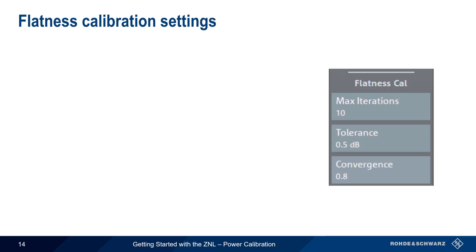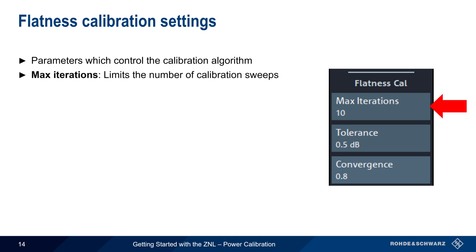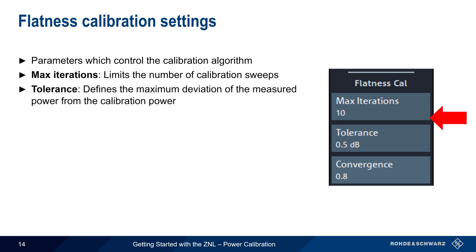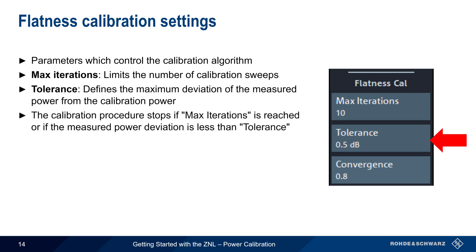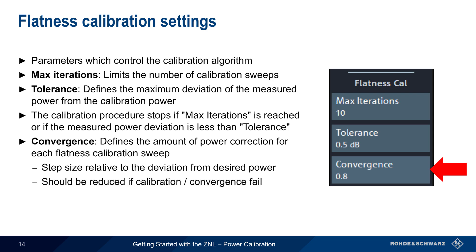The final set of configurable parameters are those for flatness calibration, and these parameters control the calibration algorithm. Max Iterations limits the number of calibration sweeps, and Tolerance defines the maximum allowable deviation of measured power from calibration power. The iterative power calibration routine will stop once either Max Iterations is reached, or when the deviation of measured power is less than the Tolerance value. Convergence defines the allowable change in power correction for each flatness calibration sweep — specifically, the step size relative to the amount of deviation from the desired power level. This value should be reduced if calibration or convergence fails. In most cases, the default values will not need to be changed.